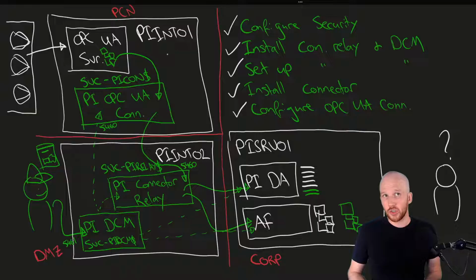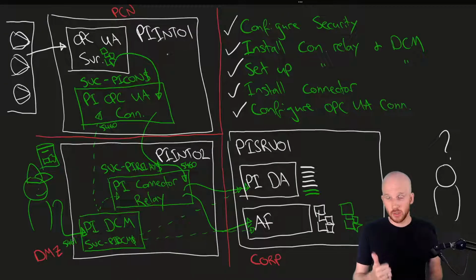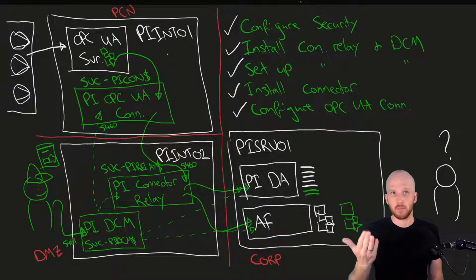The disadvantage of the OPC UA connector. So a few disadvantages. One is failover and redundancy. It does not support failover and redundancy. It does support history recovery. So if any of the tags on the OPC server side are historized, it will recover history, but not on demand. It'll only do it if connection goes out. When it comes back, it'll recover the history.